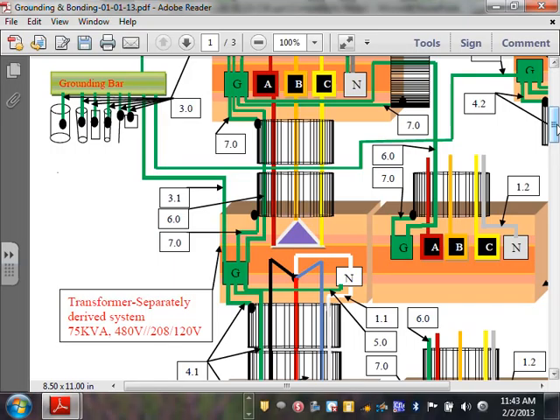Anybody have done it? Where you took one conductor, it would act as your equipment grounding conductor and your bonding conductor. They always do us. That's what I mean. Yeah. But there's a point to be said about that. But they look for that. What they're going to tell you probably is you did not install a grounding electrode conductor, and you're depending on the equipment grounding conductor to act as the grounding electrode conductor, right? That's probably you're missing a grounding electrode conductor. You say, well, it's doing dual function. No, it's not allowed to do dual function basically. But I see the point though.